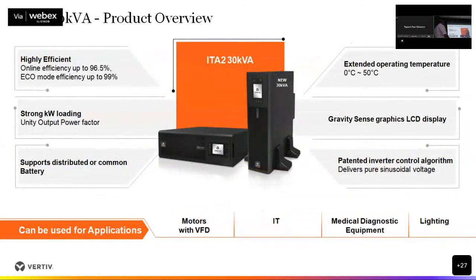This is one more launch we have done, a 30 kVA UPS with best efficiency of 96.5%. One advantage of this UPS is that it comes with a temperature compensated battery charger, where you can even install your batteries at a moderate temperature, without air conditioning. The charging profile is controlled, and it can extend the battery life by adjusting the charging voltage. It can be paralleled up to 4 systems again, with 50 degrees Celsius operating temperature, and kVA equals kilowatt, which delivers the maximum power density in a smaller footprint.